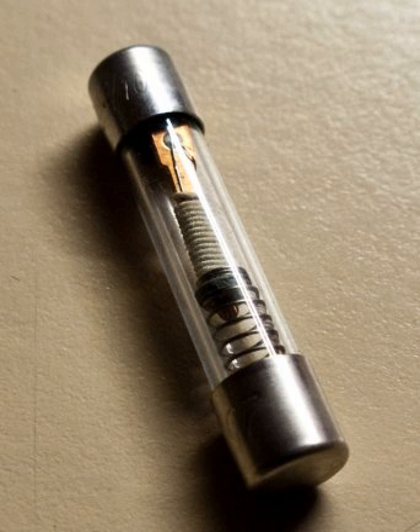Topic: Fuses compared with circuit breakers. Fuses have the advantages of often being less costly and simpler than a circuit breaker for similar ratings. The blown fuse must be replaced with a new device, which is less convenient than simply resetting a breaker and therefore likely to discourage people from ignoring faults. On the other hand, replacing a fuse without isolating the circuit first, as most building wiring designs do not provide individual isolation switches for each fuse, can be dangerous in itself, particularly if the fault is a short circuit.